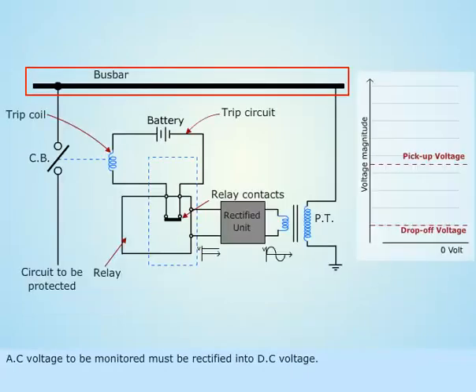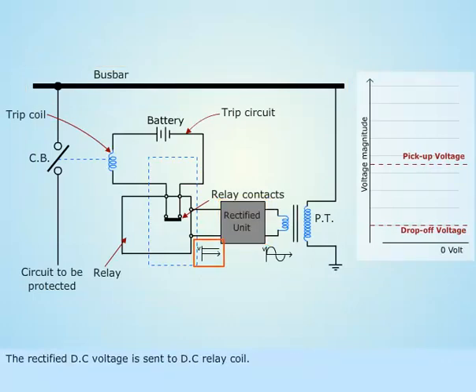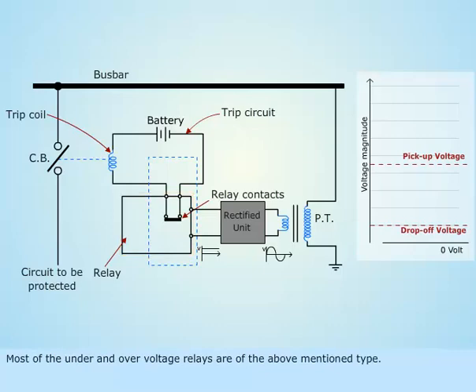The AC voltage to be monitored must be rectified into DC voltage. The rectified DC voltage is then sent to the DC relay coil. Most under and over voltage relays are of this type.